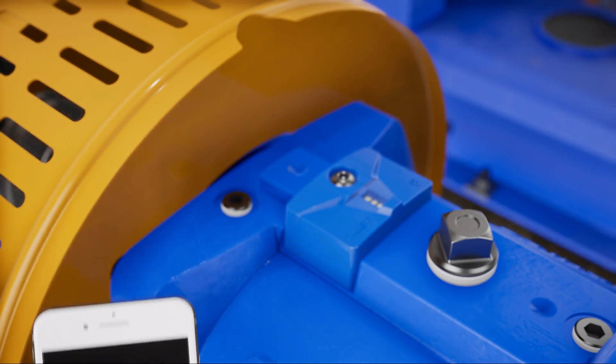When activated, the i-ALERT2 takes a baseline vibration reading for 25 equipment run hours. This baseline is used to set high vibration alarm levels. No programming is required by the installer. You can also set the alarms to your own standard through the mobile application.